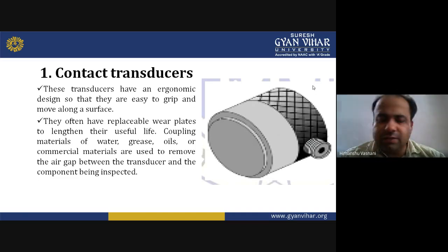So they often have replaceable wear plates to lengthen their useful life. Coupling materials of water, grease, oil, and commercial materials are used to remove the air gap between the transducer and the components being inspected. There are various coupling elements like water, grease, and oil, or some kind of synthetic material, used to remove the air gap between the transducer and the component being inspected.